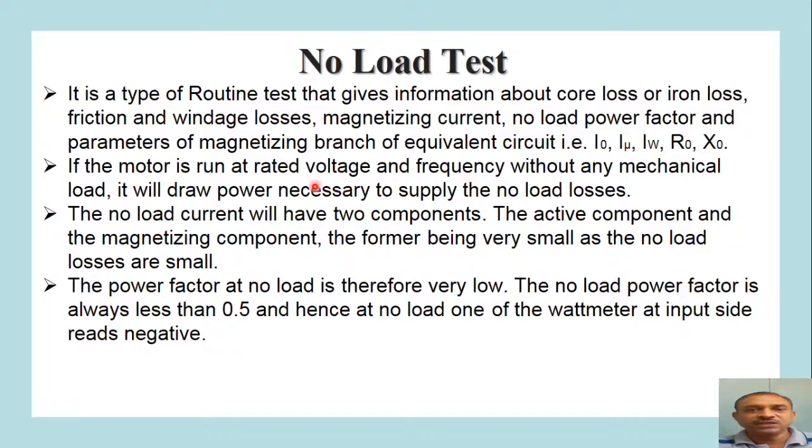Now the basic condition to conduct this test is that the motor is to be run at the rated voltage and rated frequency without any mechanical load on it, so that it draws the power which is necessary to supply the no load losses.